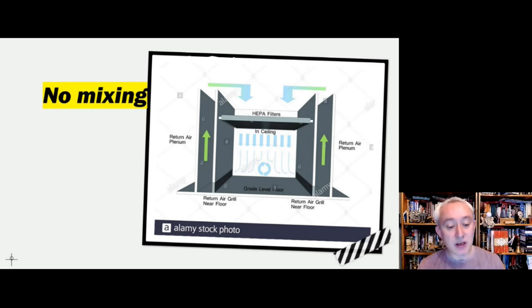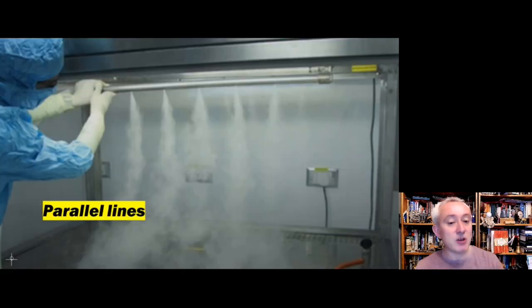So the other important concept you can see from this next image, which is from an airflow study—so it's a typical airflow study using a smoke curtain as you'd find carried out in the facility—is that the design intent is that air should make a single pass through the grade A zone with a piston-like effect.